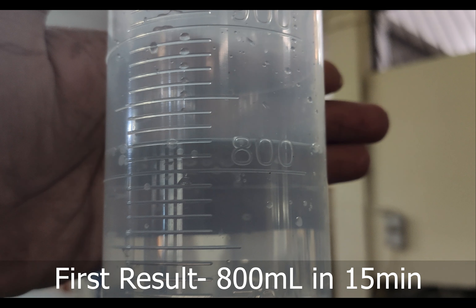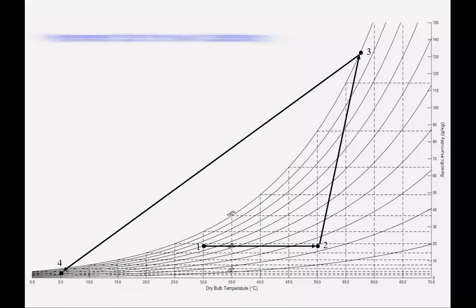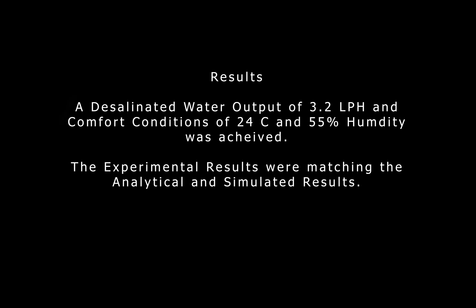The first set of results showed 800 ml of desalinated water generated in 15 minutes. The psychrometric chart for the air conditioning part of the unit was also plotted. The final results obtained were a desalinated water output of 3.2 liters per hour, and comfort conditions of 24°C and 55% relative humidity were achieved. The experimental results were matched with analytical and simulated results.